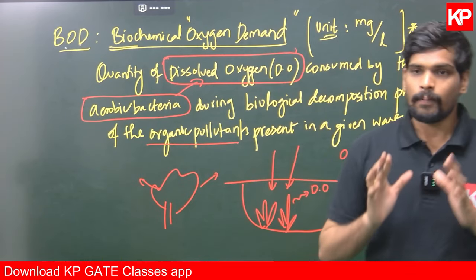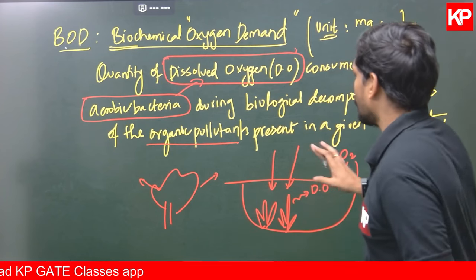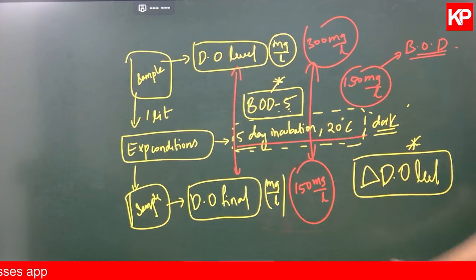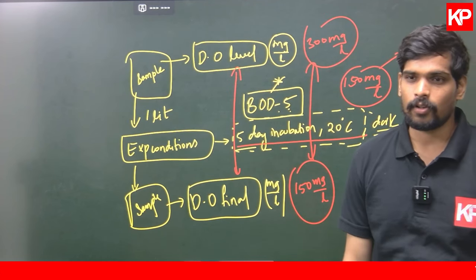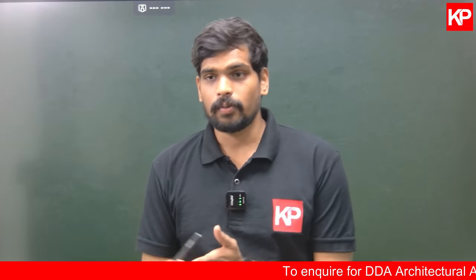So that's the understanding of biological oxygen demand, BOD. Just to add to this, as I told you, this is how it is measured: the change in the dissolved oxygen level over a 5 day incubation period, and that's what BOD5 is. Now, there are two or three things in addition to whatever we discussed that you need to understand.